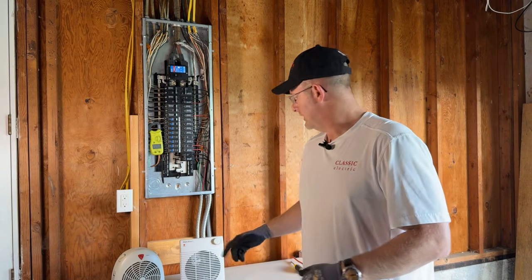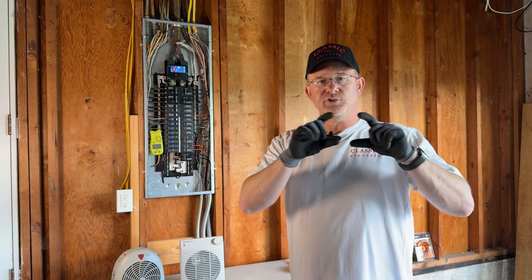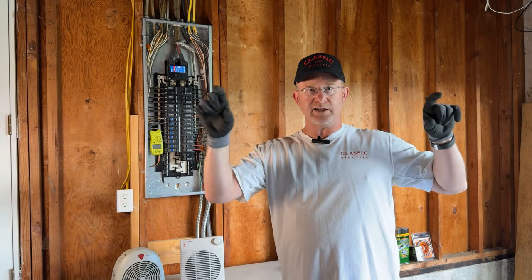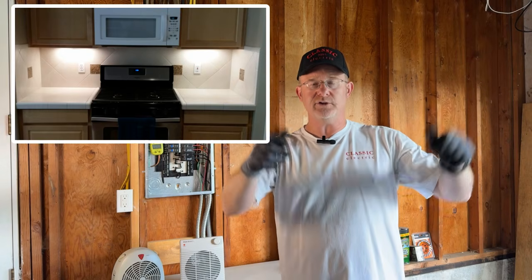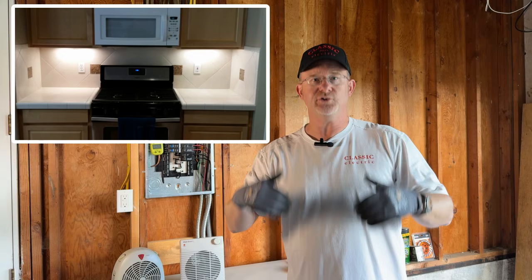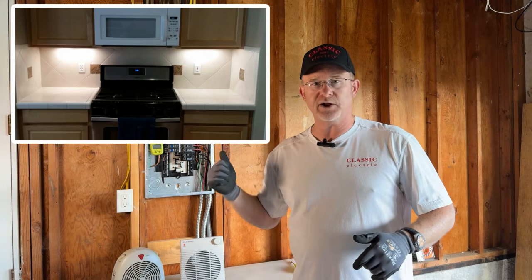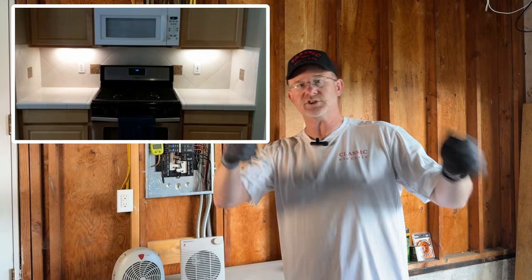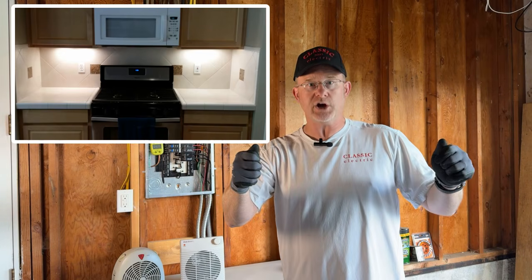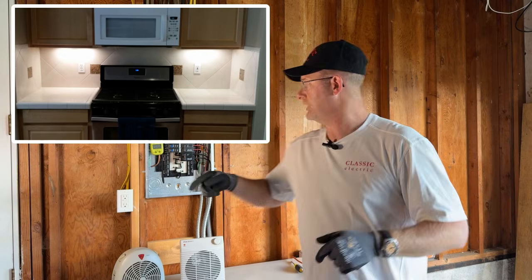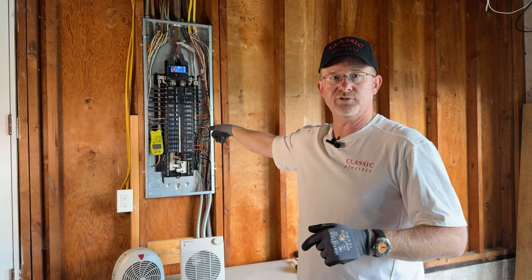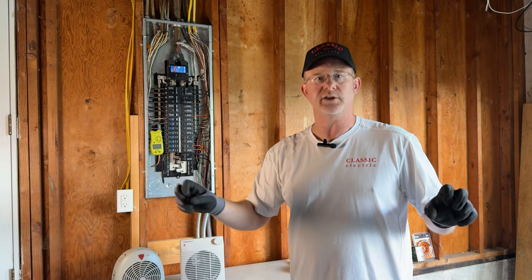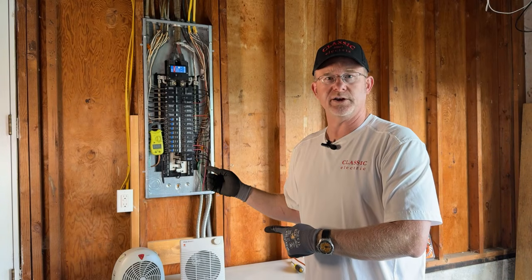Another one that's similar is if you take your hood vent above your stove in the kitchen, you got the cute little hood vent, a little skinny little guy like this, and you take that out and you put a microwave in place. Well, it's the same scenario. You're cooking food, you're heating food. It's the same thing as the heater here and the hair dryer. You're supposed to have a dedicated circuit for your microwave if you've got it above the stove. So if you take the hood out and you put the microwave hood combination in, you're supposed to have a dedicated circuit. So again, you're going to go from here and run a dedicated circuit over. Otherwise, every time you start up the food, the lights and everything else that was on the old hood circuit trips the circuit, for the same thing that we've got going on here.